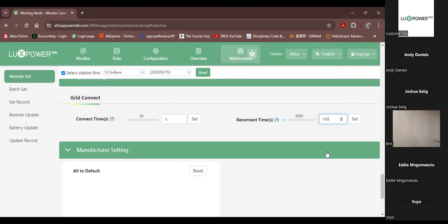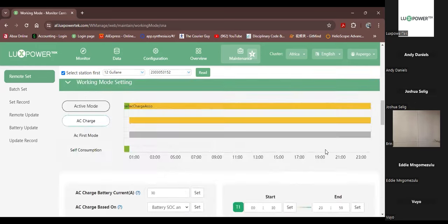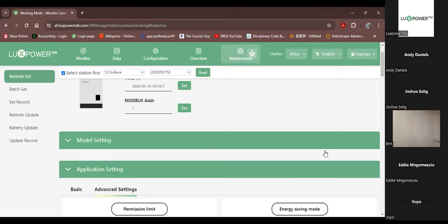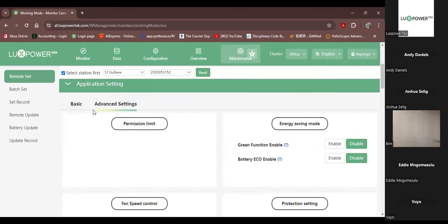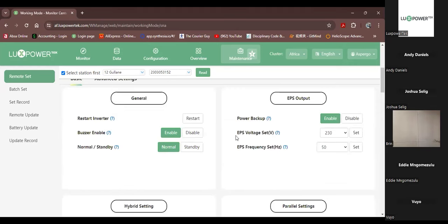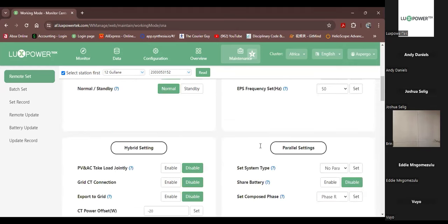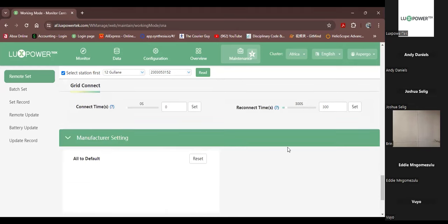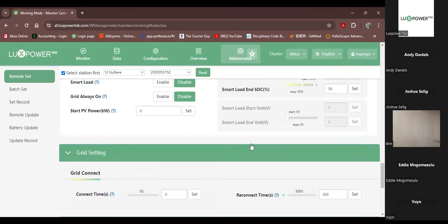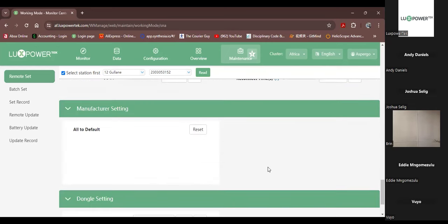Now, on the LXP range, we can set the grid connection voltages. On the SNA, we can't do that. The LXP we can. So it's predetermined on the SNA. If the voltage goes below a certain value or higher than a certain value, it goes to off-grid, as well as if the frequency goes out of range. All right, and then you guys all know this button here, all to default. That puts the whole machine back to the default setting.